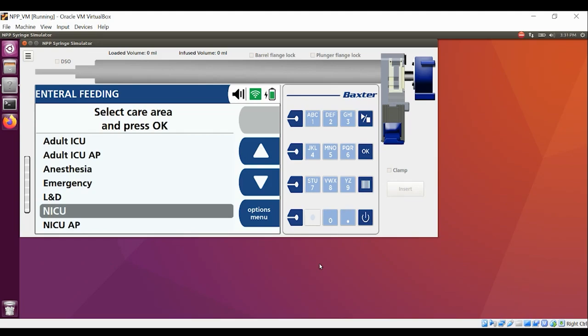Other things that the NICU is concerned about is the ability to deliver very concentrated fluids or medications at very, very low rates because they need to keep the volumes down for those little patients. We want to make sure that we don't fluid overload these patients. When we talk about high accuracy, we talk about doing things like priming to remove the mechanical slack and cinch up the gears. This improves the startup time and reduces the stiction, which is present in all syringes that we load onto any syringe pump. Remember that startup time and stiction have to do with the syringe, not the pump. But the pump does offer the ability to improve that when we use the prime feature.